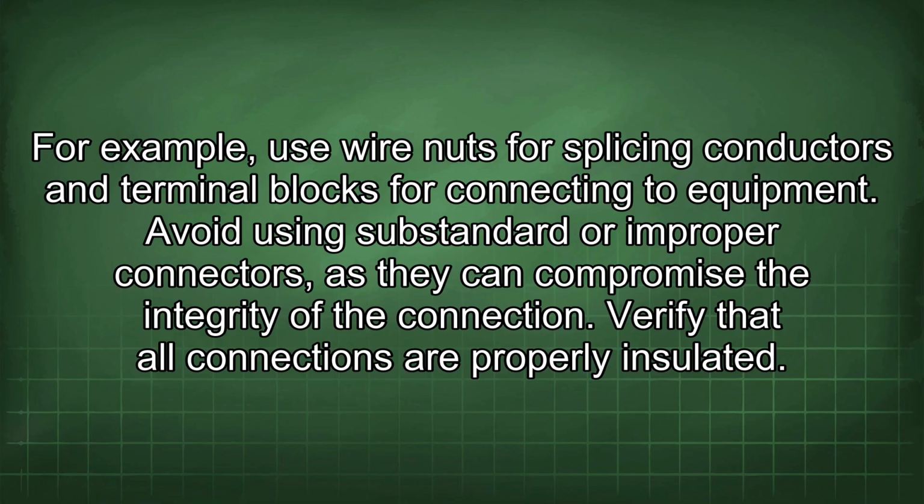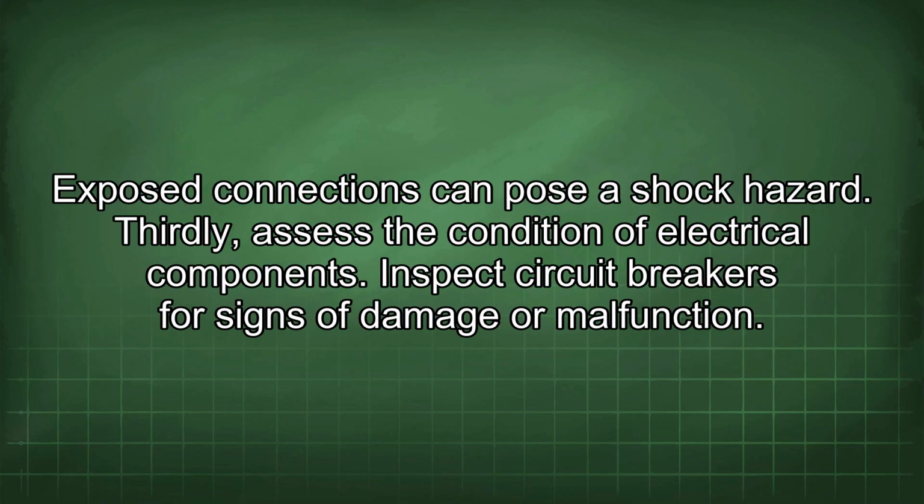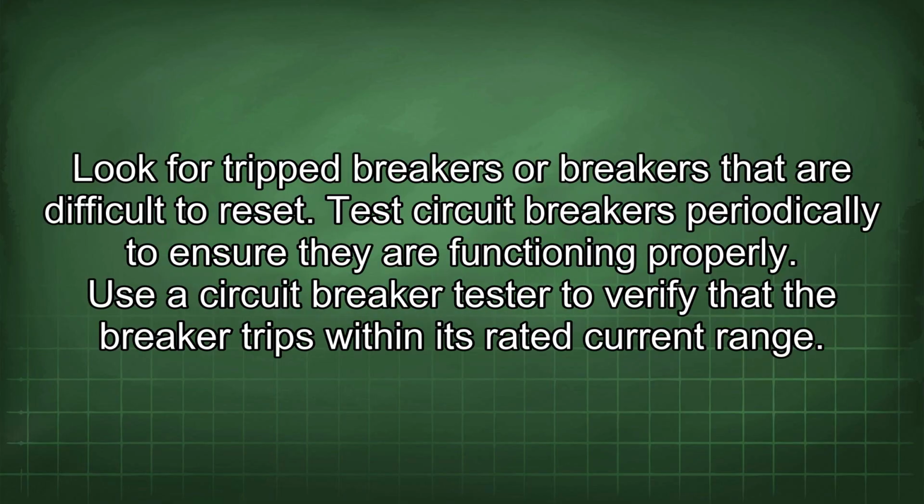Verify that all connections are properly insulated. Exposed connections can pose a shock hazard. Thirdly, assess the condition of electrical components. Inspect circuit breakers for signs of damage or malfunction. Look for tripped breakers or breakers that are difficult to reset. Test circuit breakers periodically to ensure they are functioning properly.